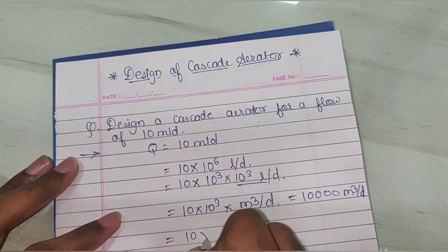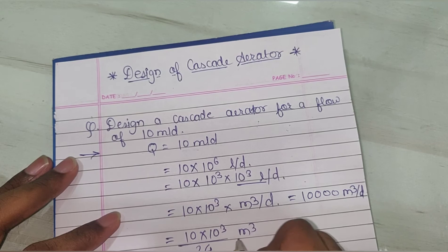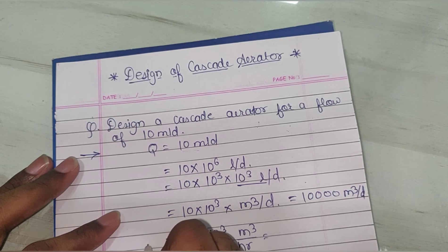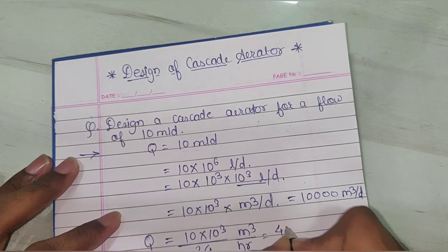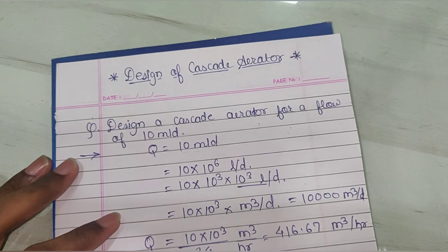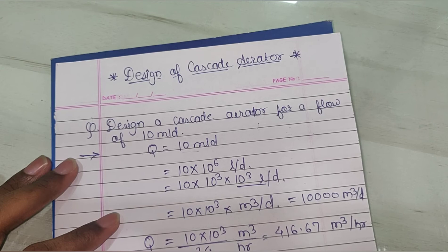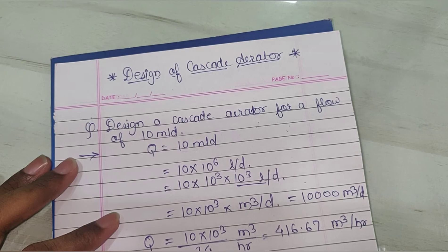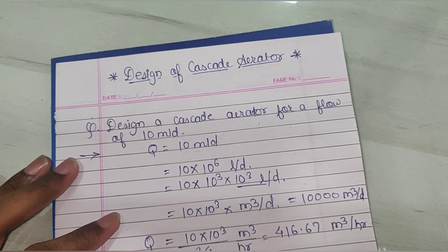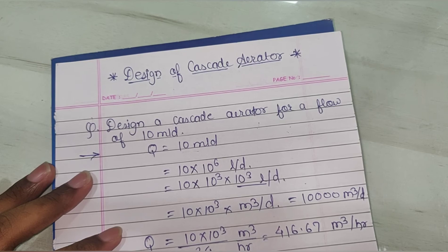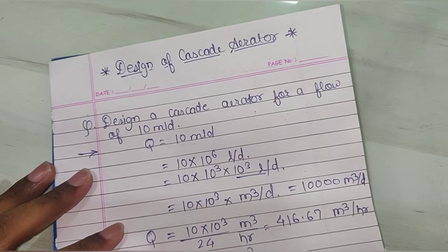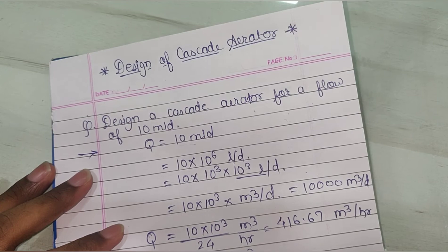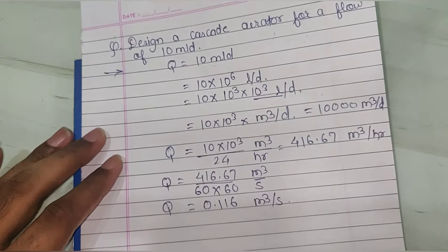Now I have to convert this value into meter cube per hour. So 10 into 10 raised to 3 divided by 24 gives the flow rate in meter cube per hour. After calculating this, you will get the value of Q as 416.67 meter cube per hour. Now we also need Q in meter cube per second. We know 1 hour equals 60 minutes and 1 minute equals 60 seconds, so dividing gives approximately 0.116 meter cube per second.